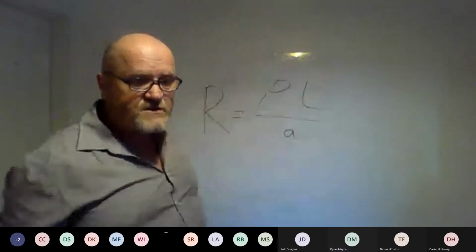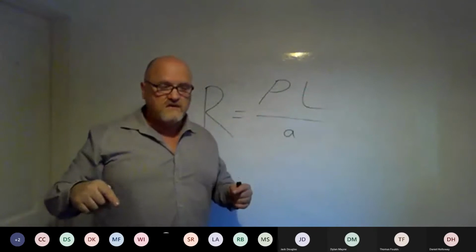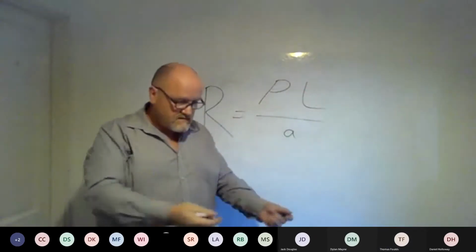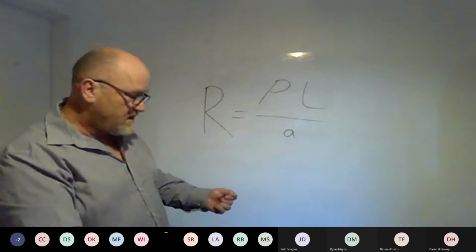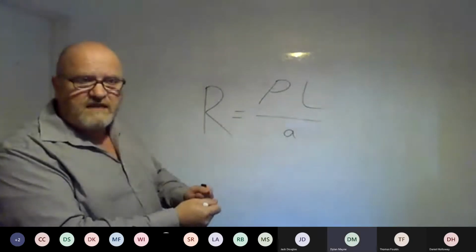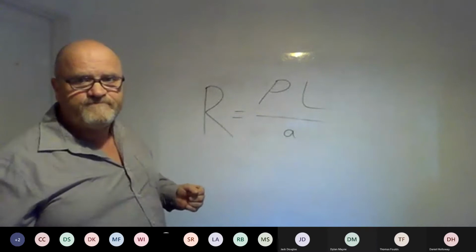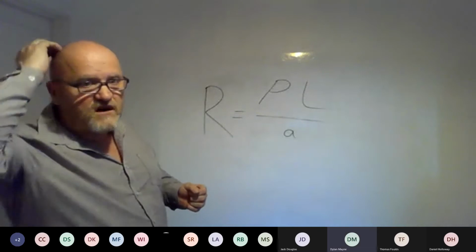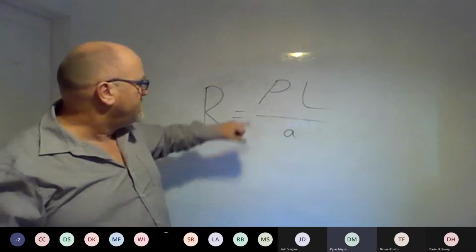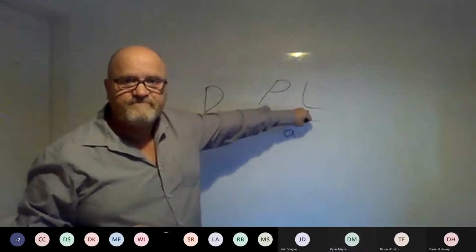When you've got drawings in front of you and you're designing these circuits, you want to know what the resistance reading will be when you test it. If I put this 100 meters in, what should the reading be when I test it? If it's higher than that, what does it tell me? Not right. There's something wrong, loose connections. If it's lower than that, I've got some serious problems. But it starts from this formula.